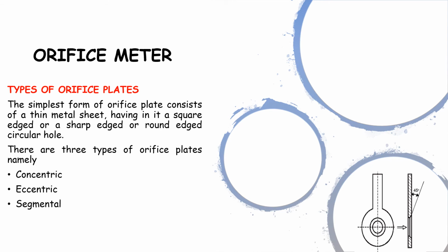The most common orifice plate is a square edge concentric bore design, and this type of plate is manufactured by machining a precise straight hole in the middle of a thin metal plate. The concentric plate is also very easily reproduced at a relatively low cost. It is also used to measure a wide variety of single-phase liquid and gas products, typically in conjunction with flange taps.